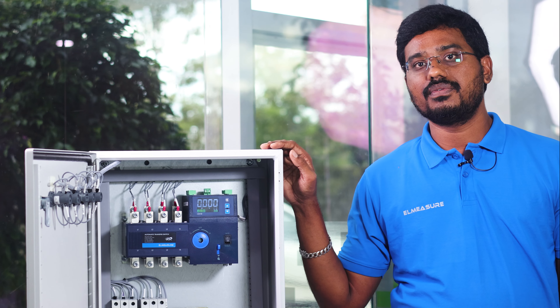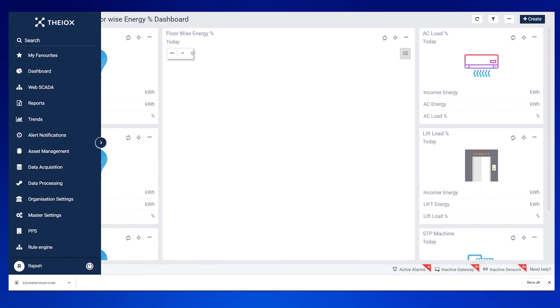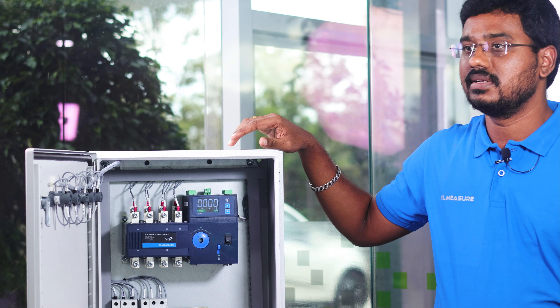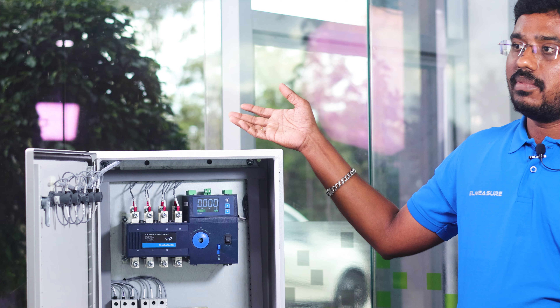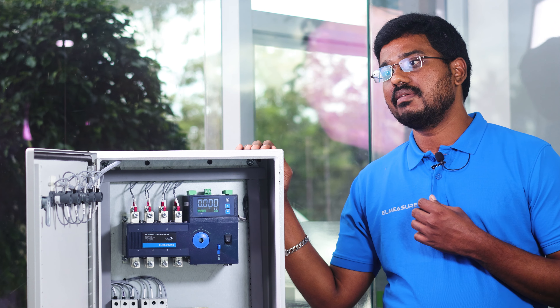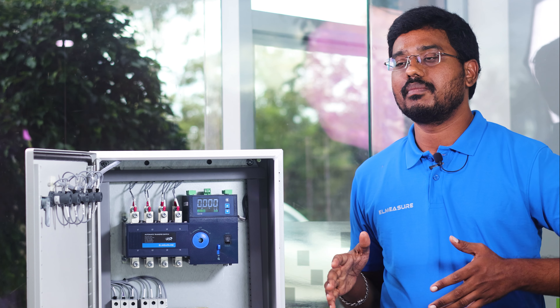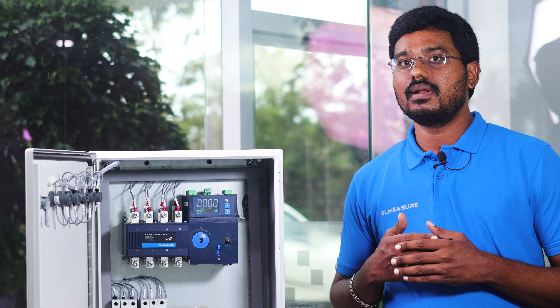Communication options include both RS-485 and Wi-Fi. With these options, this is a purely IoT-based ATS. We provide a free cloud subscription for one year, allowing you to bring all incoming-side data to the cloud. For example, with a 2000A ATS, all incoming data can be pushed to the cloud for monitoring and report generation — daily, weekly, and monthly reports.